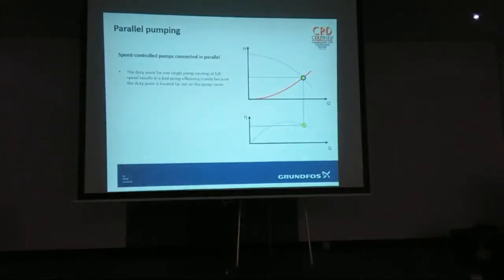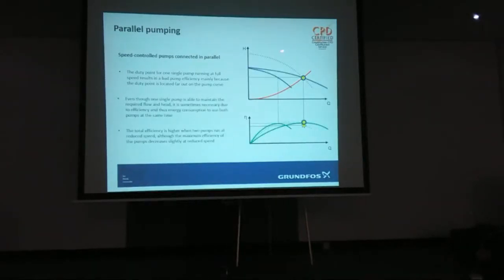Right, so speed control pumps connected in parallel. Here's one big pump working in the efficiency area, and its duty point roughly. If you've got two pumps in, we can possibly get a lower closed valve head pump. So with one pump or two pumps, we can still maintain relatively good percentage efficiency, which means lower absorbed power. And when we get the duty to this area, we've only got one pump in. If that was one 30 kilowatt pump, it's now two 15 kilowatt pumps with a third standby 15 kilowatt pump, as opposed to a standby 30 kilowatt pump. So three 15s might be cheaper than two 30s. It'd be physically smaller, and one person could probably work on it if it needed to be serviced as well.